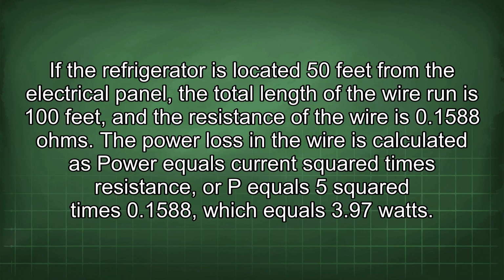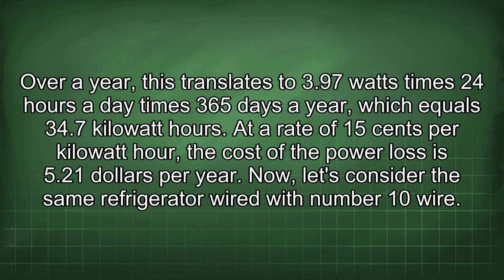The power loss in the wire is calculated as power equals current squared times resistance, or P equals 5 squared times 0.1588, which equals 3.97 watts. Over a year, this translates to 3.97 watts times 24 hours a day times 365 days a year, which equals 34.7 kilowatt hours.